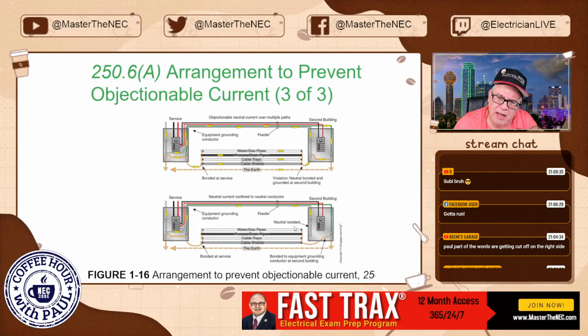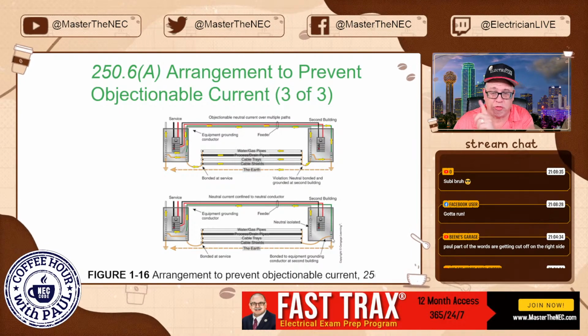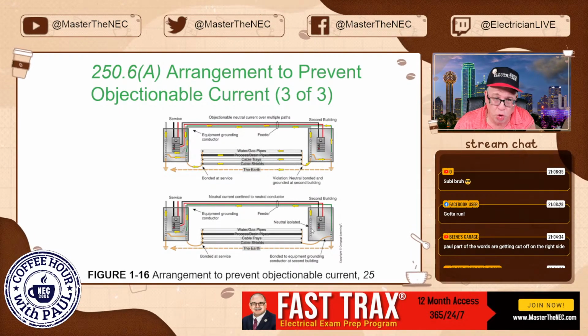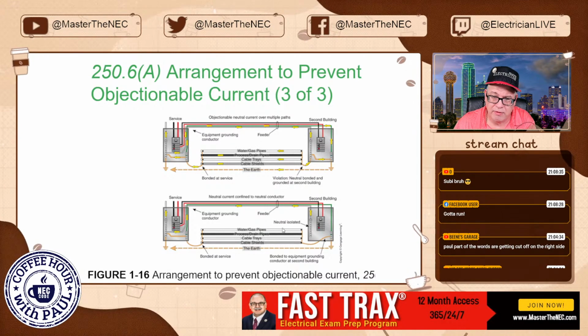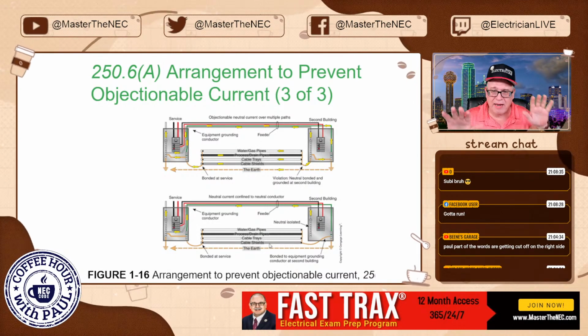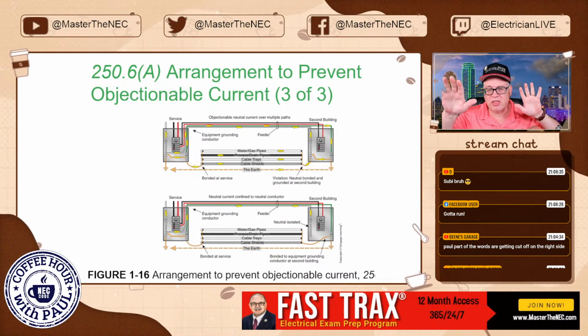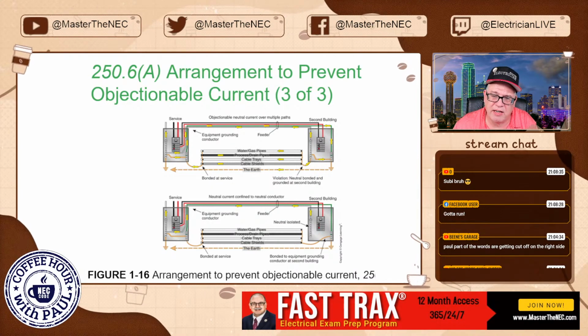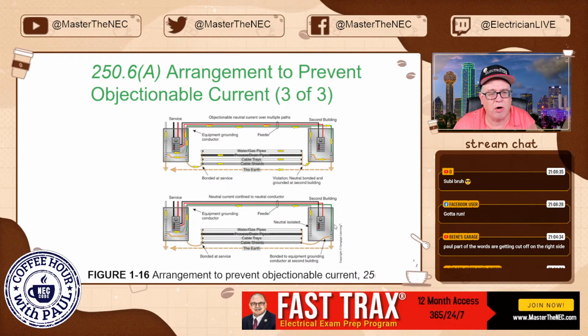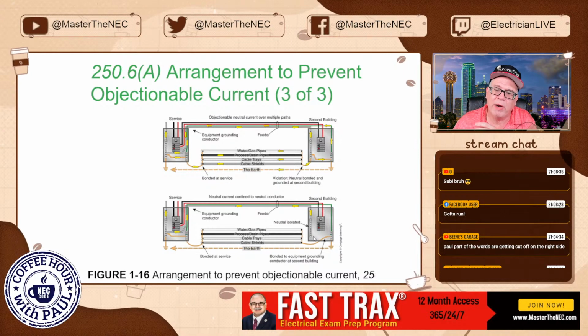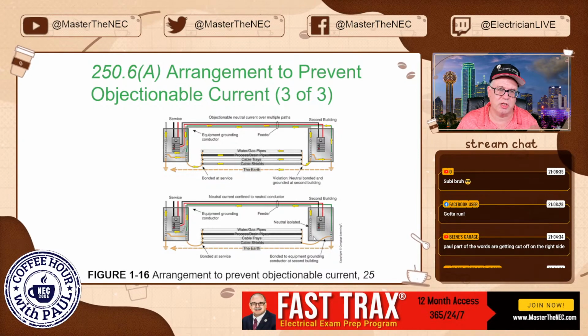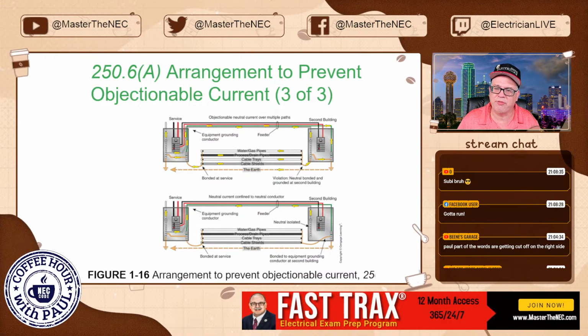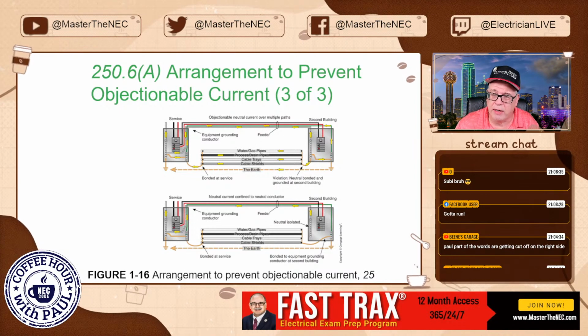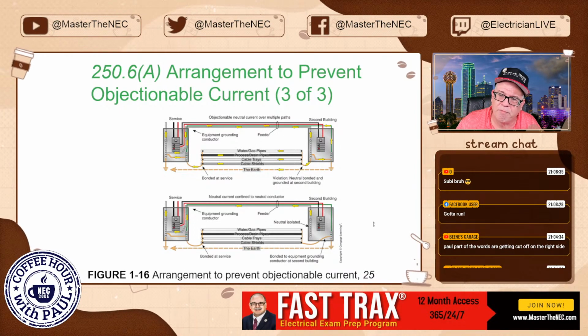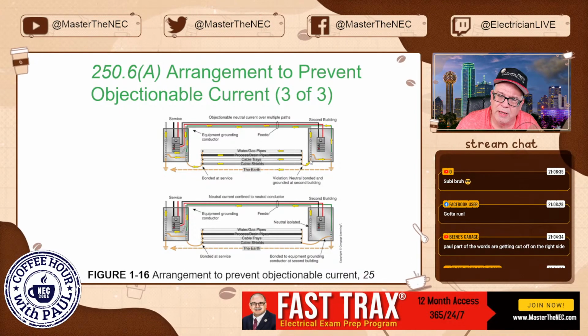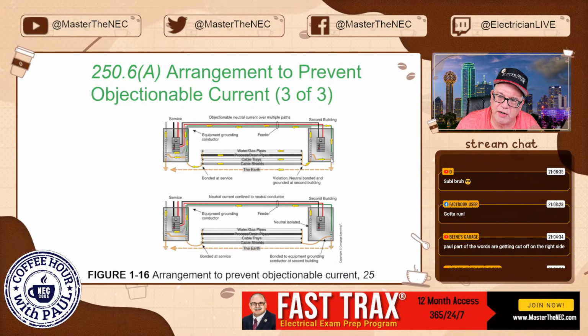You make these bond connections to the equipment ground, not to the neutral, okay? So they're all bonded. They're all at the same potential. Everything's good. Anything gets energized, it'll go back and clear the overcurrent device. We're fine. But we don't have objectionable currents circulating on paths that they weren't intended to be on. And this is a simple removal of this jumper and instead moving it over to here.